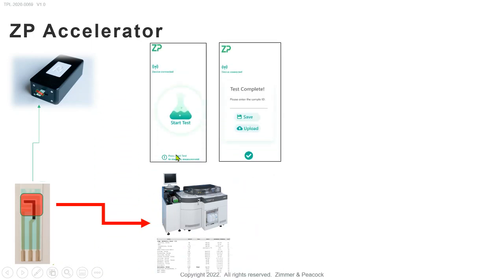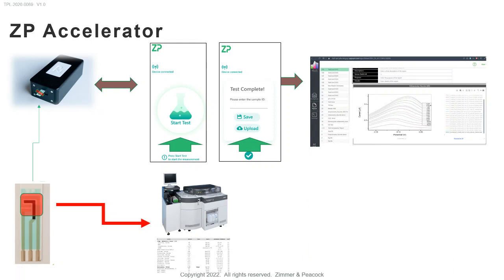Now, what we next do is we have an app that runs on Android. What that app does is it runs a method file, which essentially tells the meter what to do. So if it's a glucose sensor, it'll give it one method file. If it's a pH sensor, it'll give it another method file. But we run a method, and the meter, through a Bluetooth connection, gives the data back to the app, and we hit upload. Now at this point, our cloud technology kicks in, because the data, as long as we've got a connection to the internet, will go to our Djuli database. So Djuli is a ZP proprietary database for the saving, the analysis, and the sharing of data.